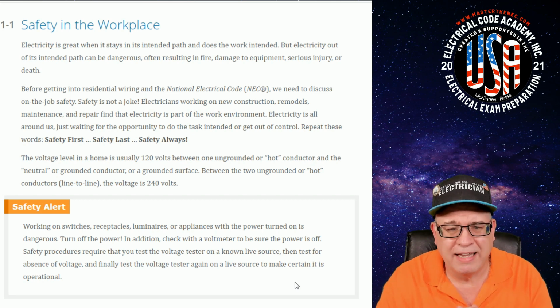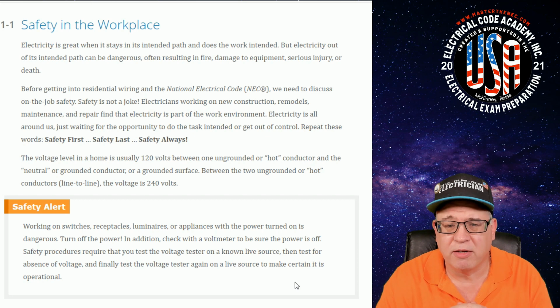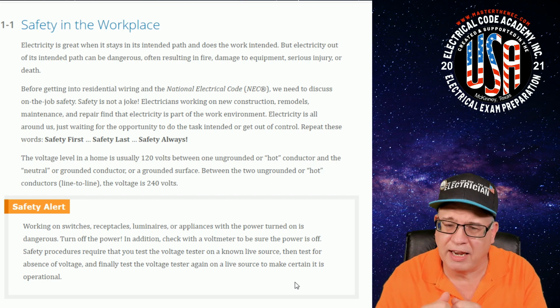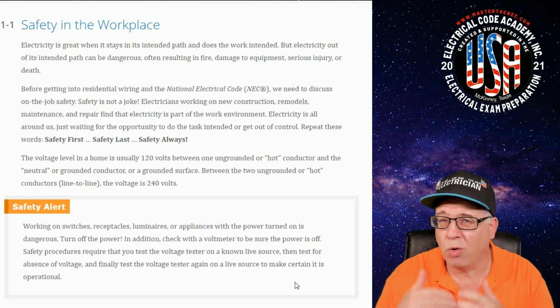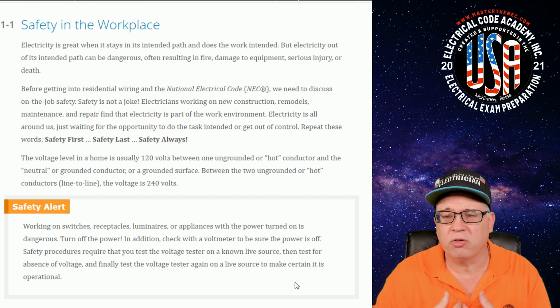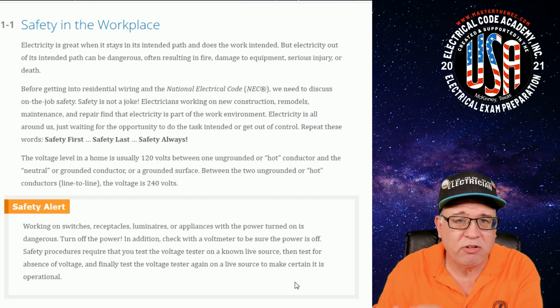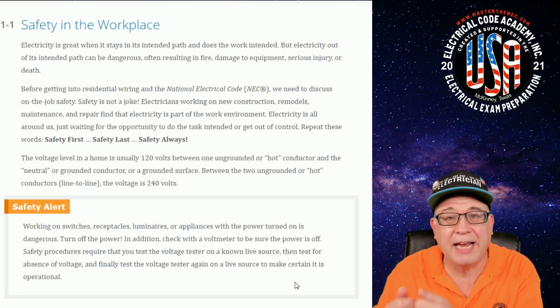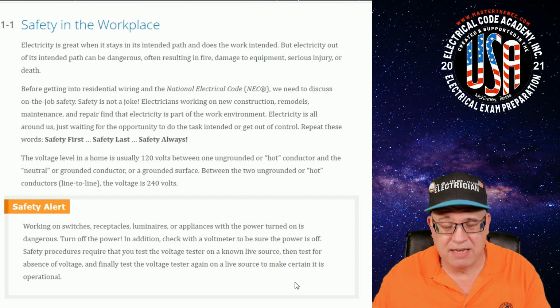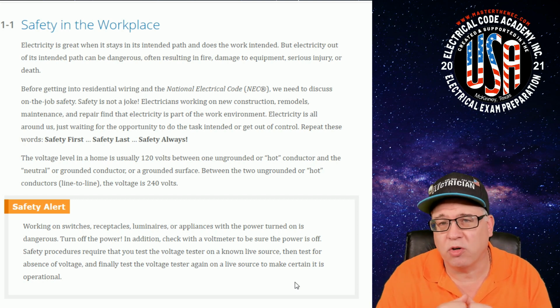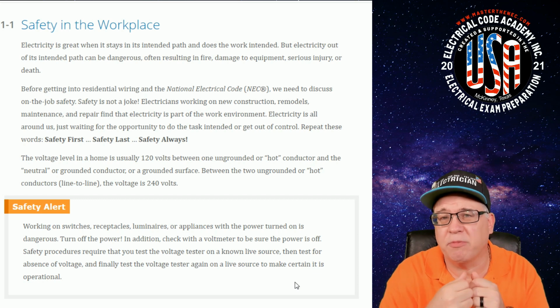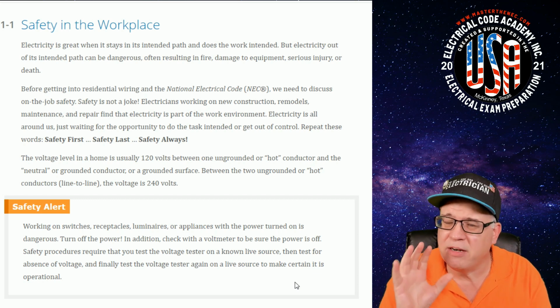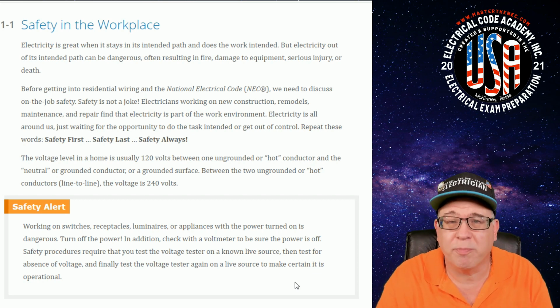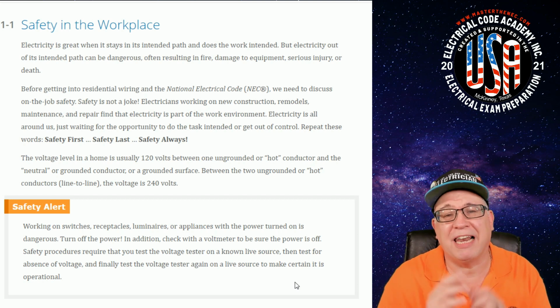Either they're lazy, or you simply go to the panel, turn off the breaker, verify with a voltmeter that the circuit is de-energized, do the work without inhibitions, then turn it back on. There's no real need to do anything hot anymore. You want a good voltmeter, and always check a known circuit first, then check the circuit you intend to work on to confirm it's been properly de-energized.